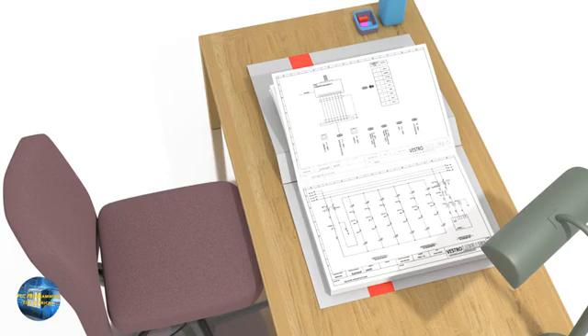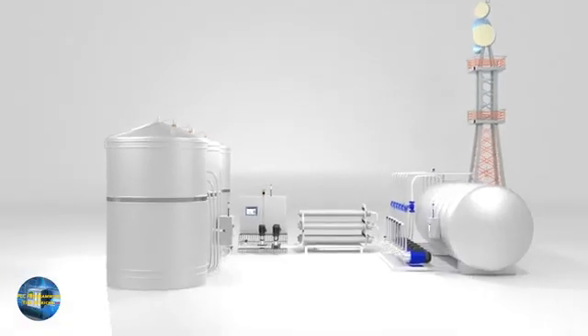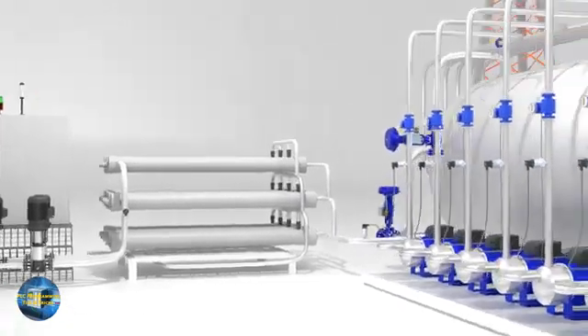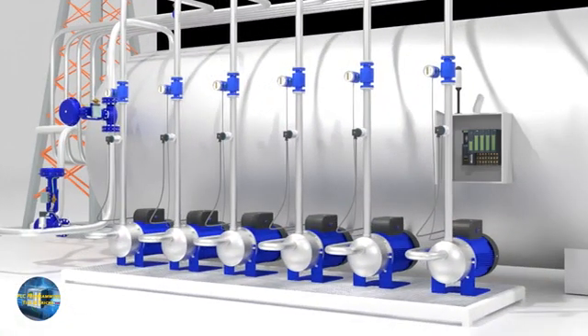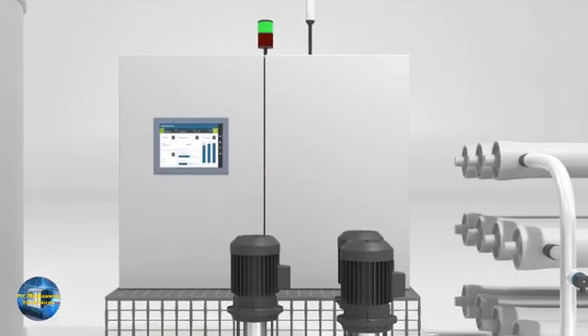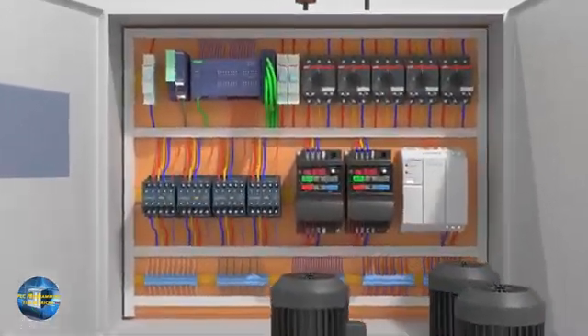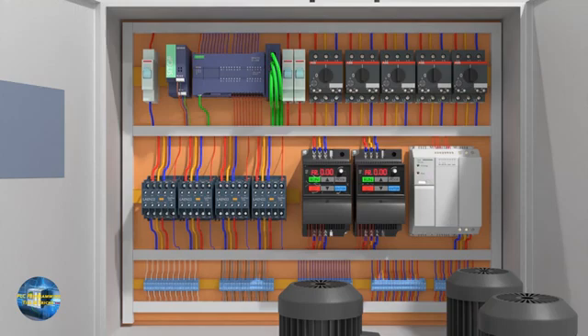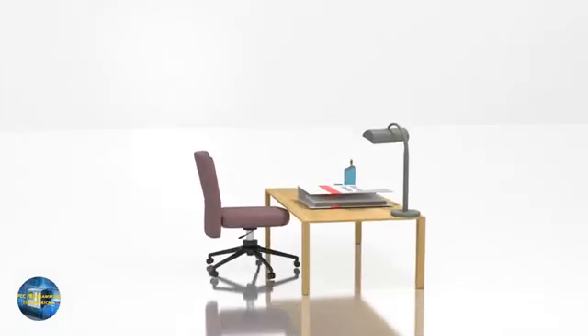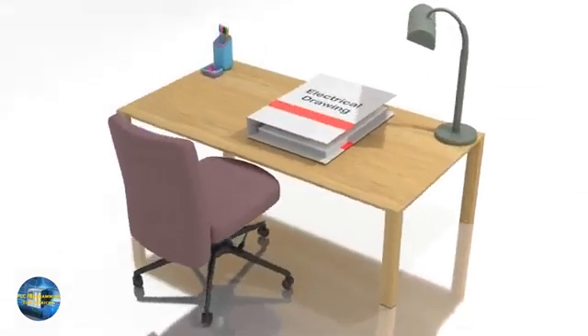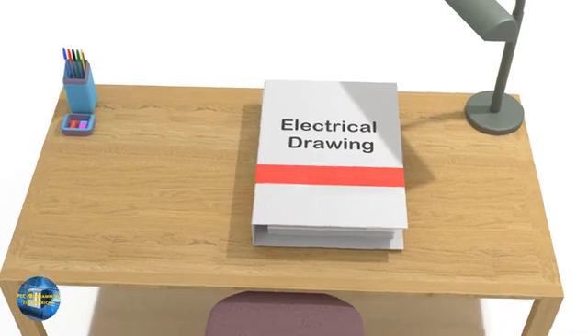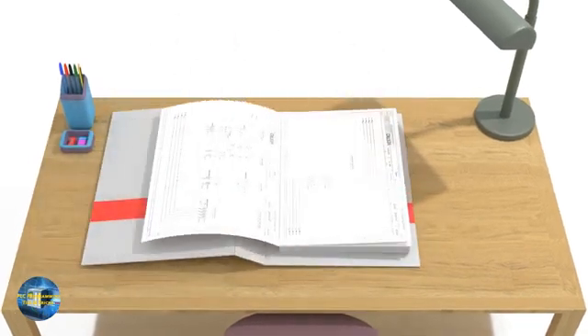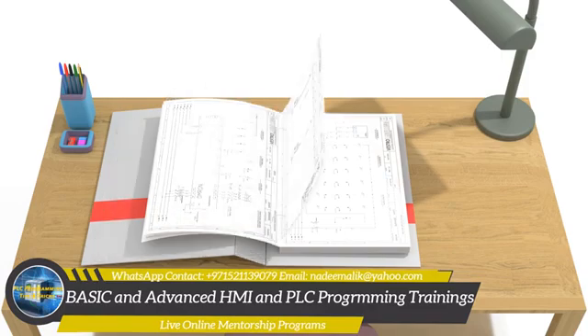Reading an electrical diagram is really important for automation, control and commissioning engineers to understand how the input and output field devices are connected to the controllers. The electrical wiring diagram shows how the PLC controller and field level instruments, sensors, transmitters, VFDs and motors are wired together. Understanding how to read it is really important to troubleshoot the machine. In today's tutorial, we will learn how to read the electrical wiring diagram using a real-world example.